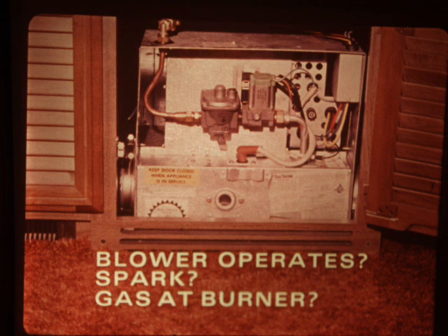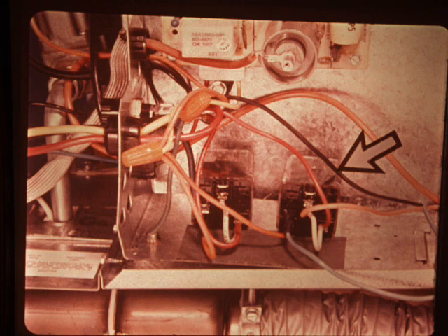Further trouble diagnosis should be based on observations made while attempting to start the furnace. Does the furnace blower operate? Is there a spark at the igniter? Is LP gas entering the burner? The furnace startup cycle begins with the blower. It must start and be up to speed before gas is admitted to the burner and ignition takes place. If the blower does not start, check the furnace blower relay. You'll have to remove the combustion chamber assembly from the vehicle to replace it. We'll cover that and other component removal procedures a little later.